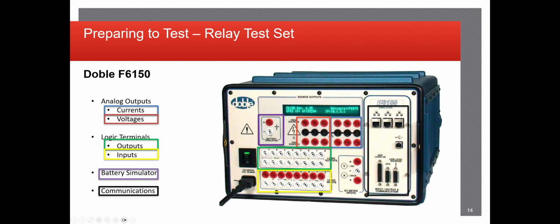Your battery simulator here in the purple, that's actually your DC voltage that you can hook up to both the logic outputs and also power up the relay if need be. Usually if you're at a site and the relay's already in the cabinet and it's got all of its wiring installed, most likely you can run some tests to make sure that the DC feed is all set and good to go and supply the relay with DC from the control house panel. But sometimes that's not an option, especially if you're doing a bench test and you can power up the relay just utilizing the battery sim.